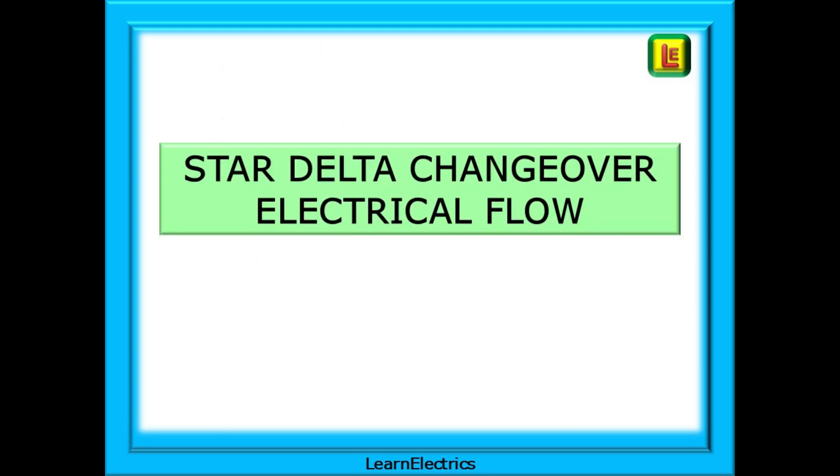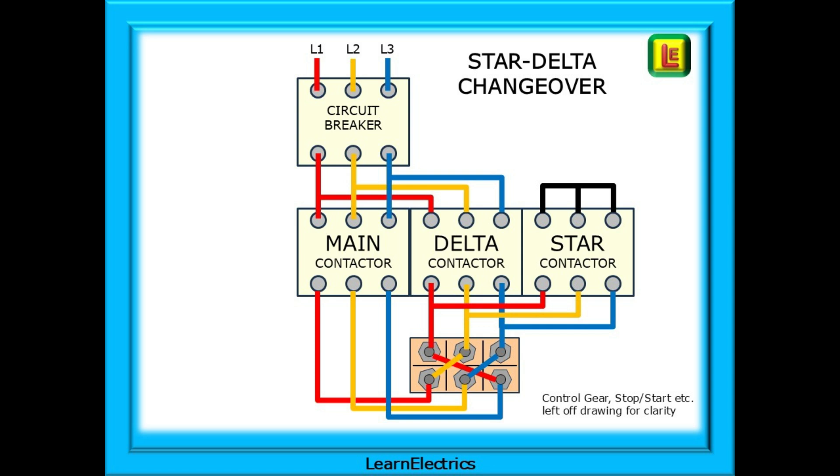Moving on, we now look at star delta changeover starters. It looks complicated at first but it's not. When we break it down, it's actually very easy to follow. Again, we've left off the control gear, stop start, etc., for clarity and better understanding of the basics. This time there are three contactors: a main contactor which must be activated in both star and delta modes. There is a star contactor which operates to start the motor turning. After a delay, the star contactor will drop out and the delta contactor will take over. Notice that there are no brass strips on the motor block, but now we have six power conductors, not three.